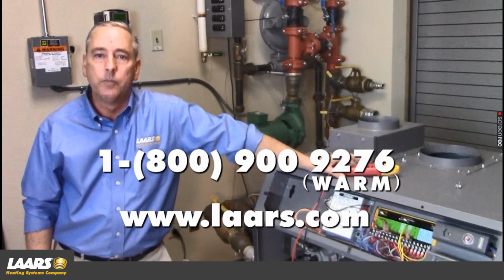Now, that time delay, when I reset the control, the blower came on, and there was a delay before the LED light went a single blink. What that is, that's your pre-purge. So we're going to run the blower, depending on the product, for about 20 seconds to clear that chamber of any residual heat. Then you'll go into hot surface ignition. You've got a warm-up period there. Again, we're looking for amperage or resistance, depending on how you're testing it. So that gives the warm-up period. Then we'll energize the gas valve.